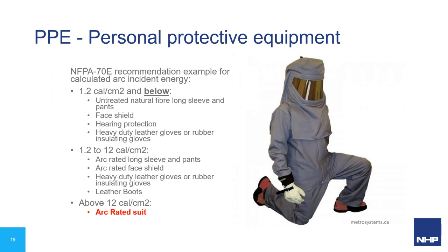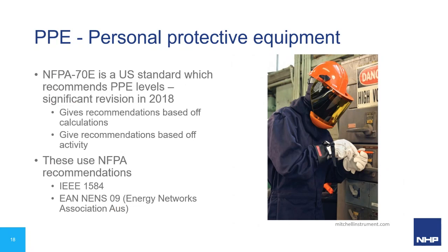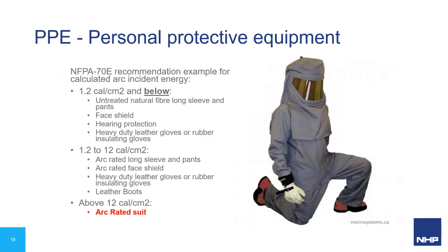Then in this 1.2 to 12 calories per centimeter squared, it's talking about arc rated long sleeve and pants, arc rated face shield. So they're like that photo in the last slide there, which I'll just go back to briefly. So that's an arc rated face shield there. Leather boots, insulating gloves.